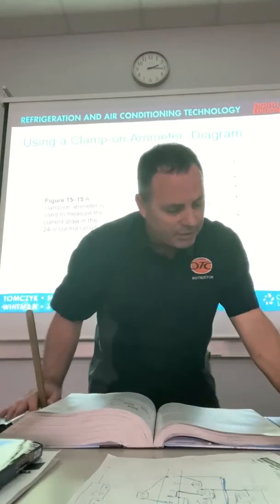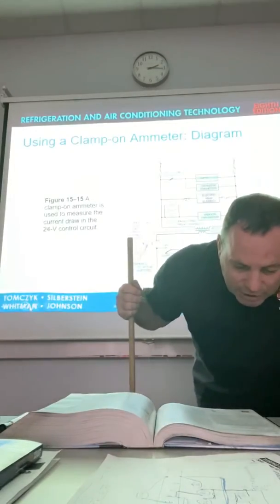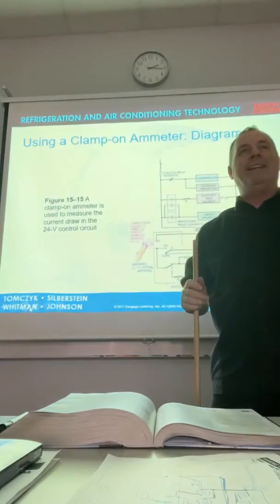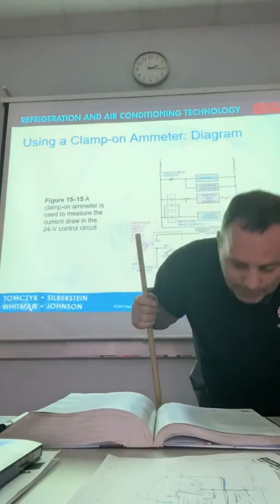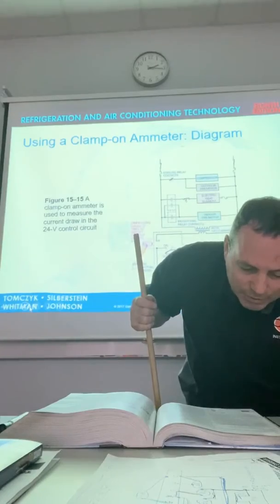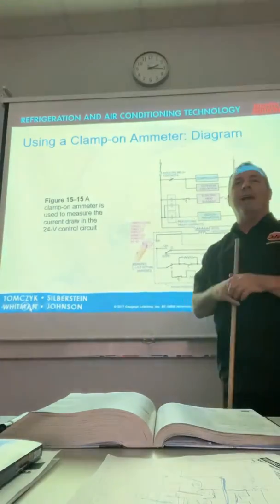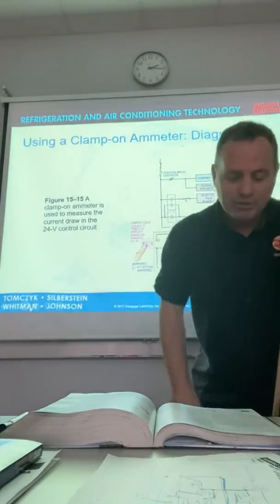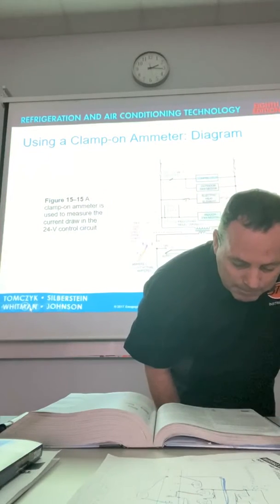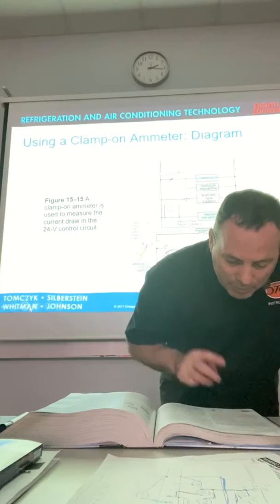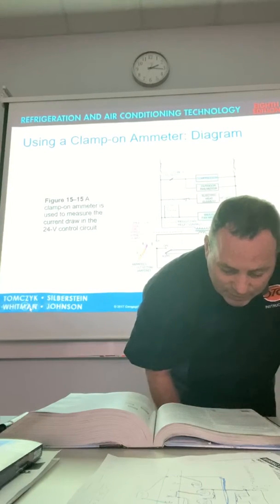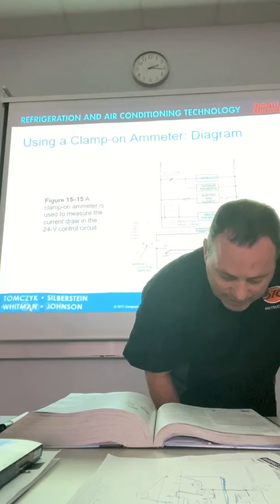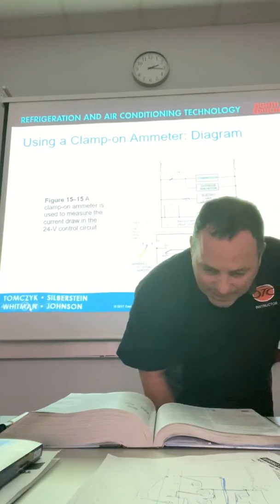Okay. Now the next page says troubleshooting low voltage circuits. You would use a voltmeter, VOM, which is your continuity, milliamps and volts. That's what you got when you came to the lab, and that's the meter you use in the lab all the time. You know all about that. So it says, remember this, when power is present at both points of a load, the component should function. If it doesn't, it's bad. You can also check continuity across it. Okay, so we did that already.